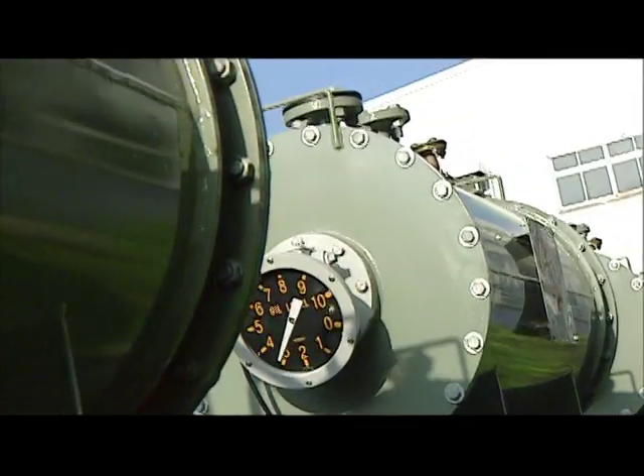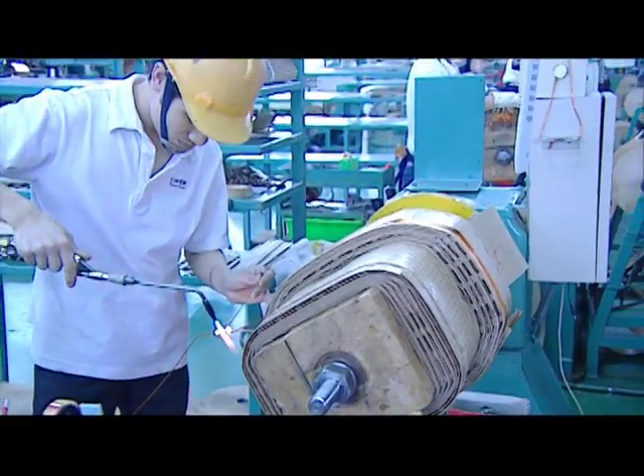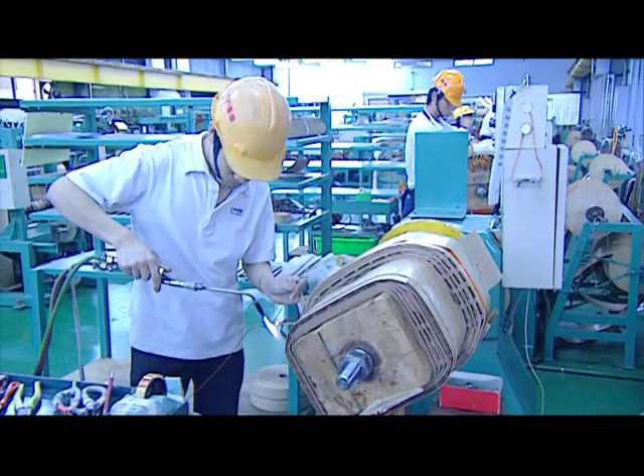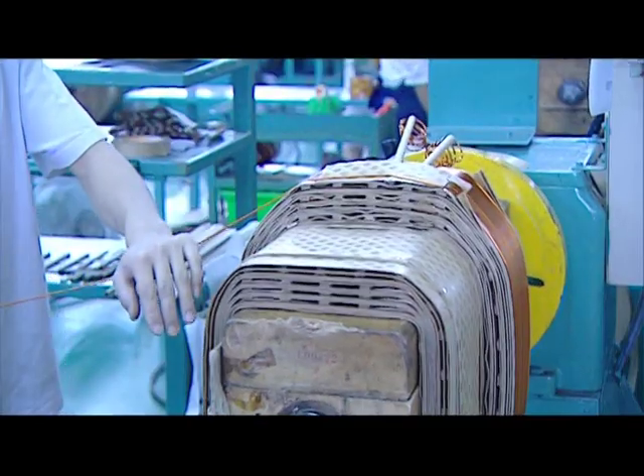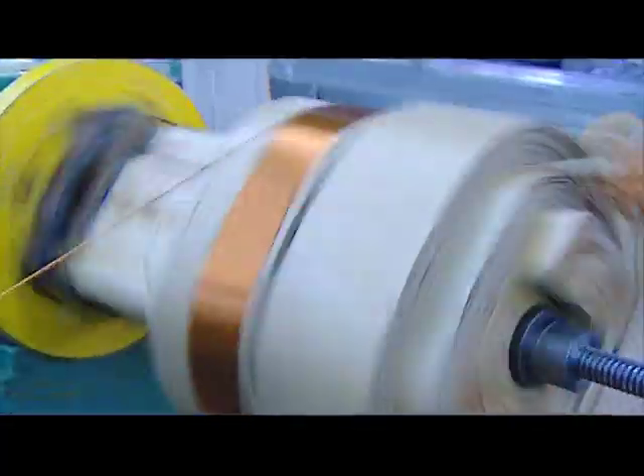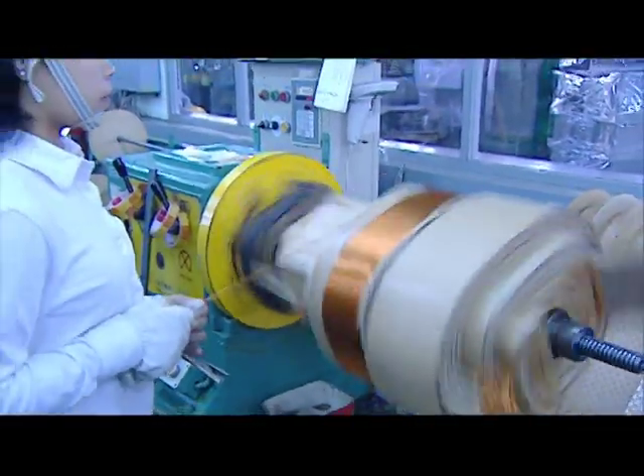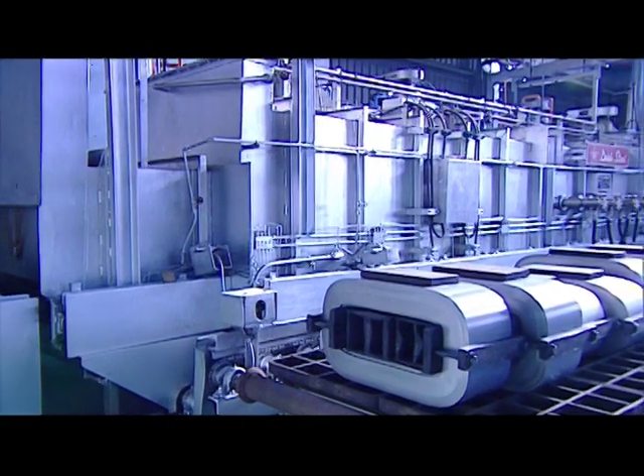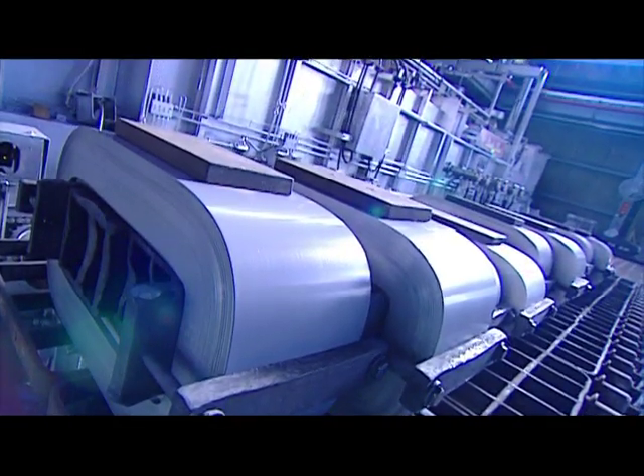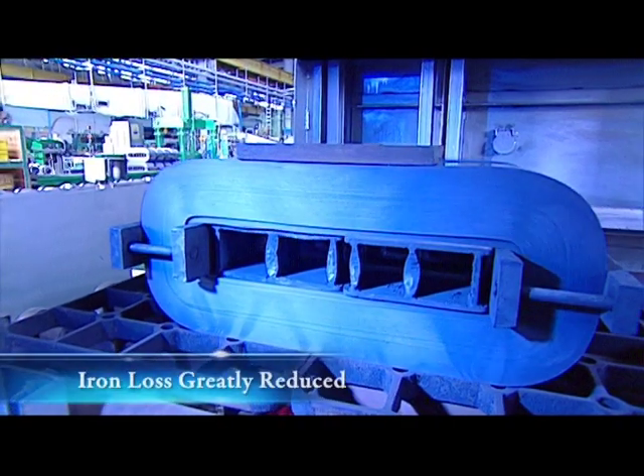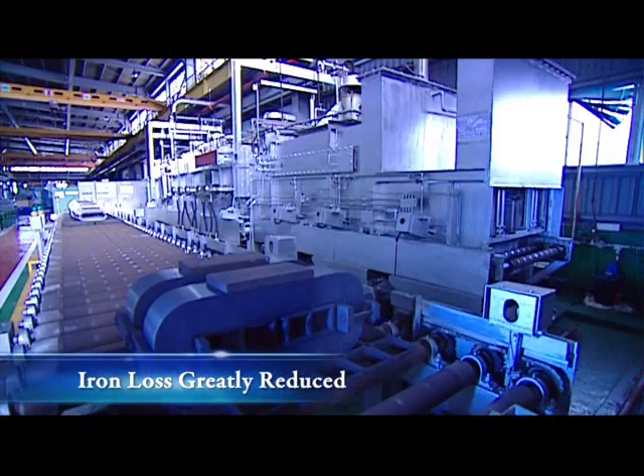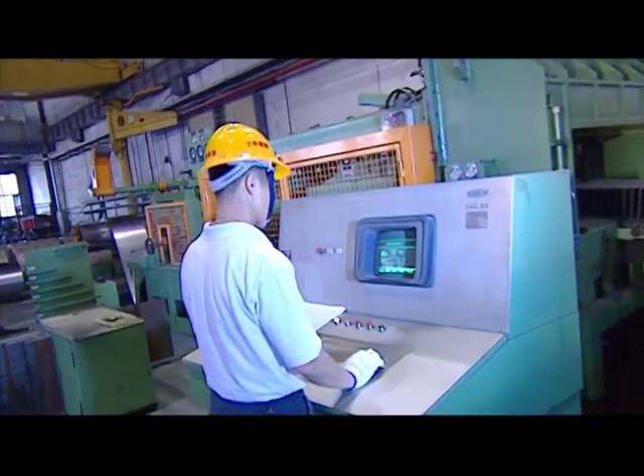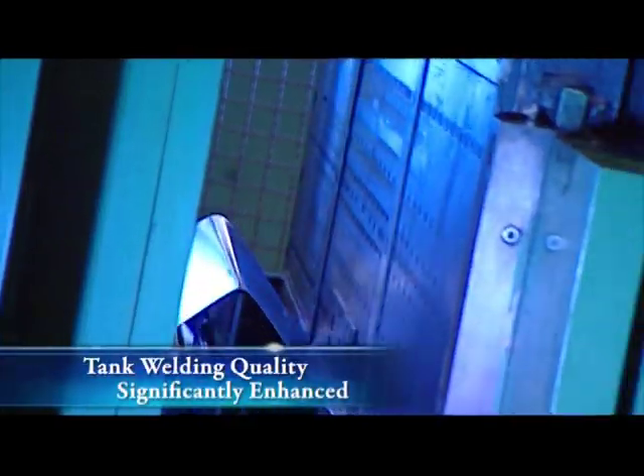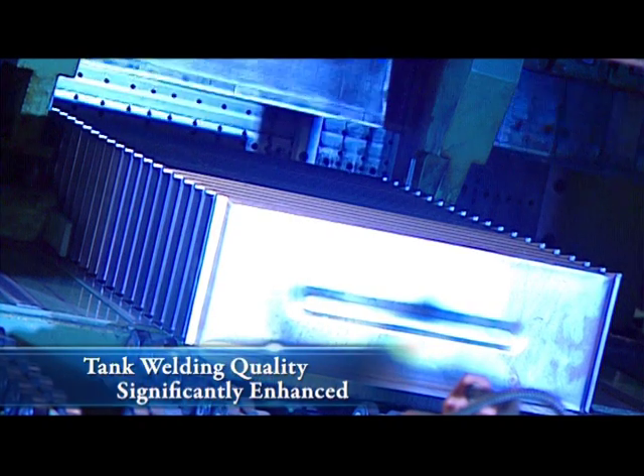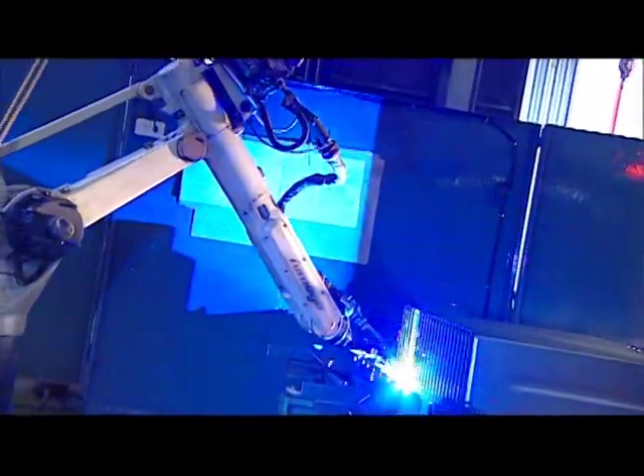Meeting the needs of its market, SHIHLIN Electric insists on quality and precision in all of its products, including using high-quality copper conductors and winding tension control for winding processes in transformer high-low voltage winding, using high-conductive silicon steel sheets in transformer cores, using an automatic round winding process and continuous feed automatic furnace to achieve annealing, using high-performance automatic tank-forming equipment and internal precision robot welder to make radiators to increase tank welding quality and enhance the leak seal.